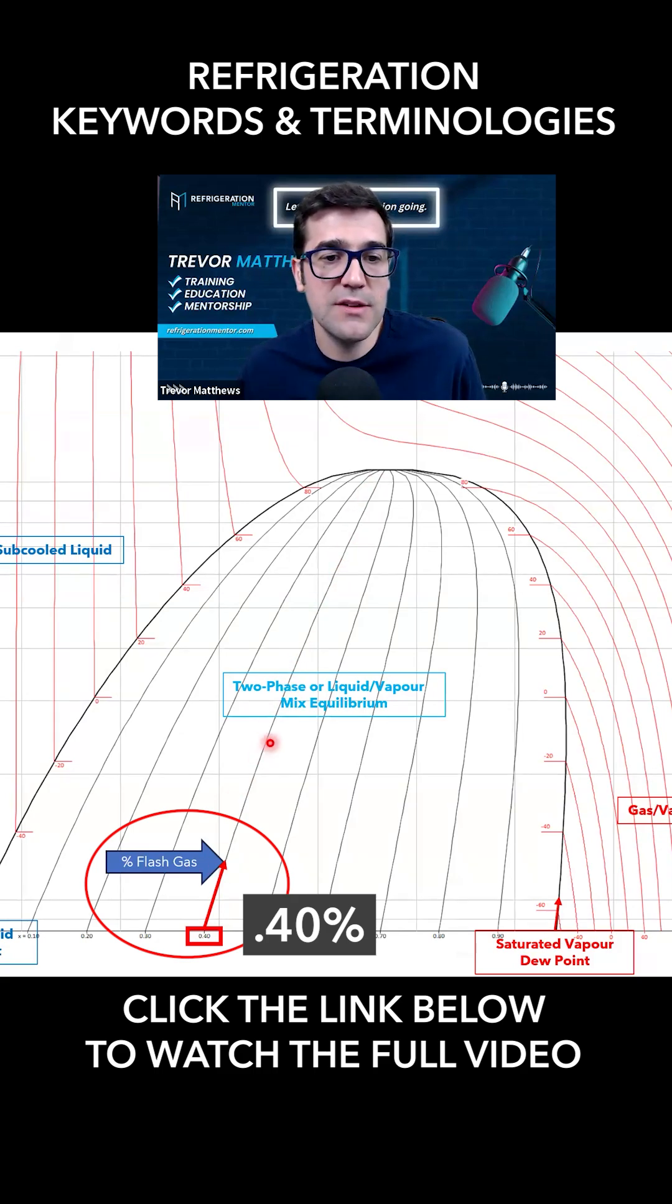There's 60% liquid. But as we start to move along here and get closer to that saturated vapor line, like this line right here, it would be 90% flash gas if we land right about here. And as we go all the way down here, this would be 10% flash gas or vapor in that two-phase mixture.